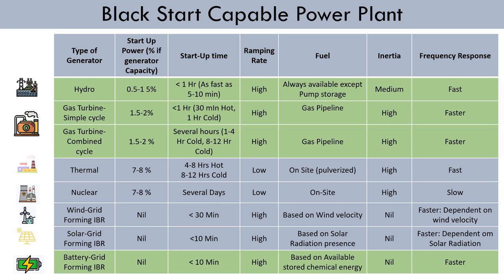Hydropower plants are widely regarded as the optimal choice for Black Start capable resources due to several key factors. Firstly, they possess the advantage of rapid startup times, allowing them to initiate power generation swiftly, which is essential for expeditious grid restoration. By harnessing the force of water flow and activating the turbines, hydro plants can promptly generate electricity. Moreover, hydro power plants exhibit minimal auxiliary consumption, enabling them to be initiated using a diesel generator set or battery bank. This feature enhances their reliability during black start operations.